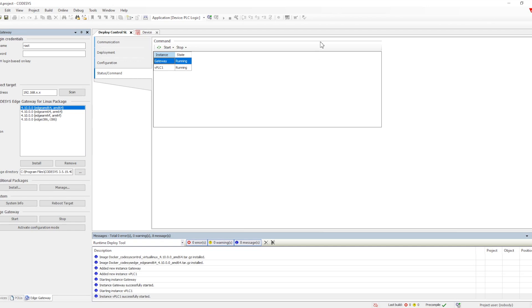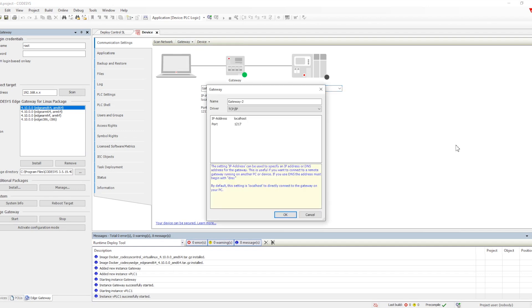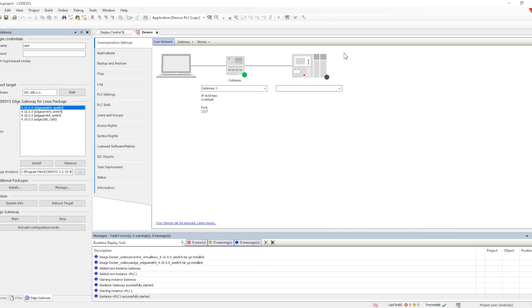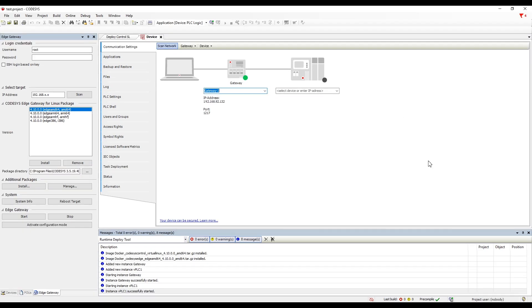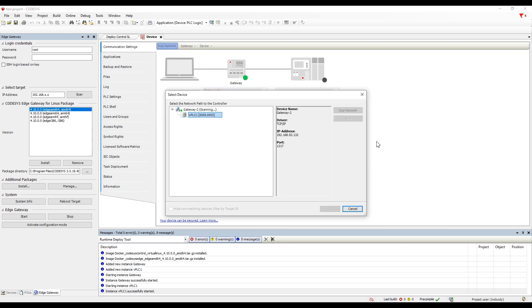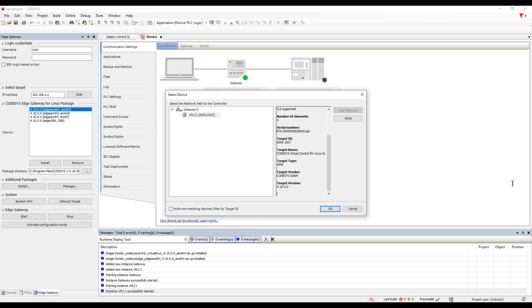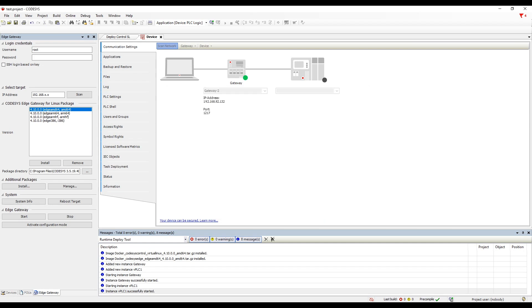Now we need to configure and start using this in a similar manner to how we normally work. We will create a gateway. Normally in Codesys we get a default gateway, but since we have deployed it on a VM we need to create a gateway again using the instance we created. We need to provide the IP address of the gateway because the gateway instance is running on that particular VM. We provide the IP and keep the port the same. Through this gateway we will be able to connect to the virtual PLC instance. When we select gateway 2 and go to scan, we are able to scan the virtual PLC, and then the process remains exactly the same as connecting with any PLC in Codesys.